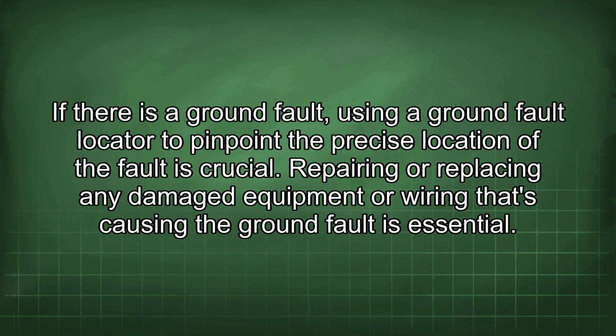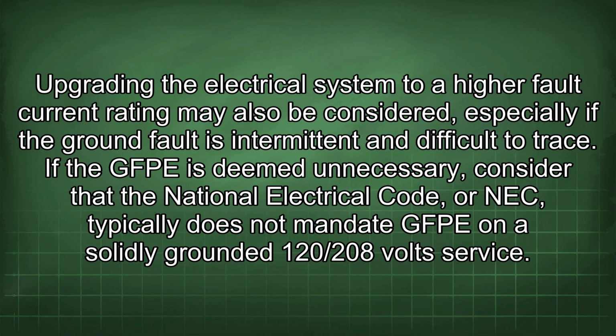If there is a ground fault, using a ground fault locator to pinpoint the precise location of the fault is crucial. Repairing or replacing any damaged equipment or wiring that's causing the ground fault is essential. Upgrading the electrical system to a higher fault current rating may also be considered, especially if the ground fault is intermittent and difficult to trace.